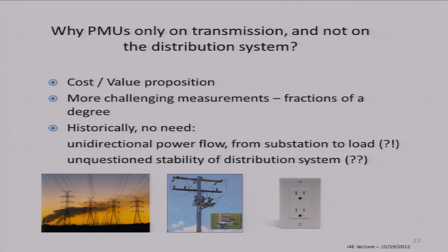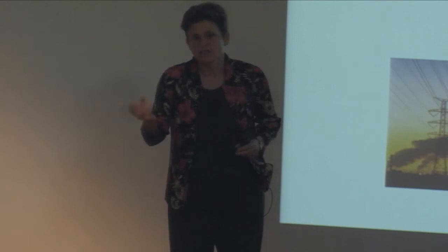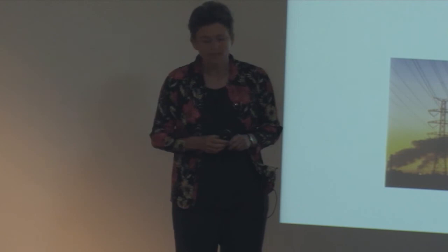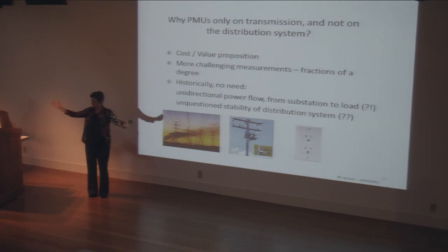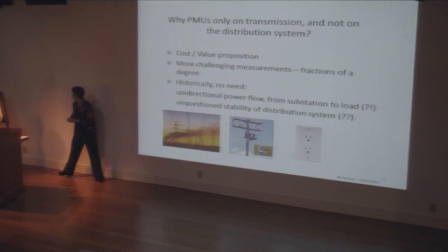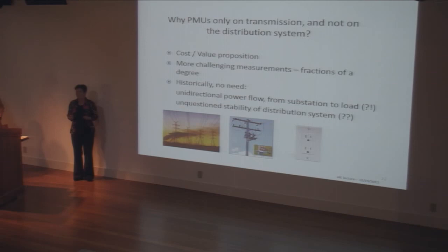Transmission PMUs are still on the order of tens of thousands of dollars. That makes sense as a diagnostic device when you're protecting an area with many megawatts of customers served. At the distribution level, the business case is not as obvious. It's also more challenging because the phase angle separations at the distribution level are much smaller.